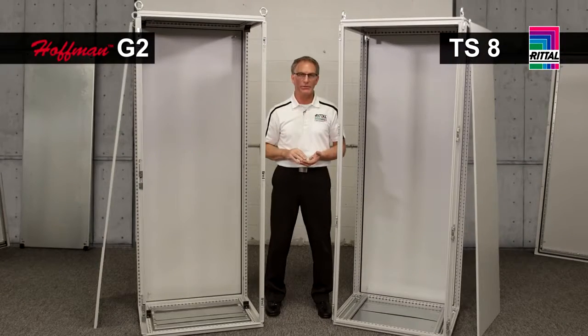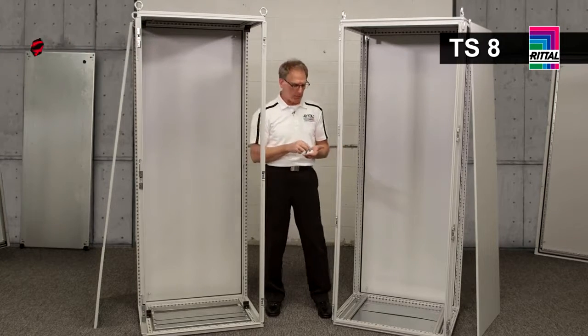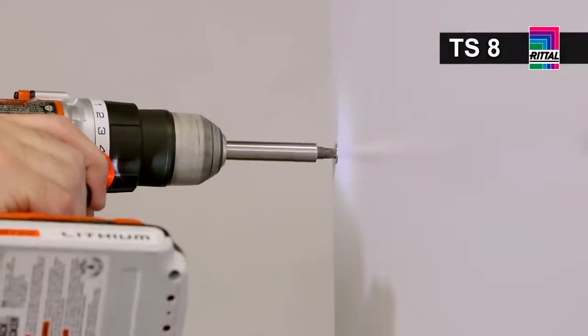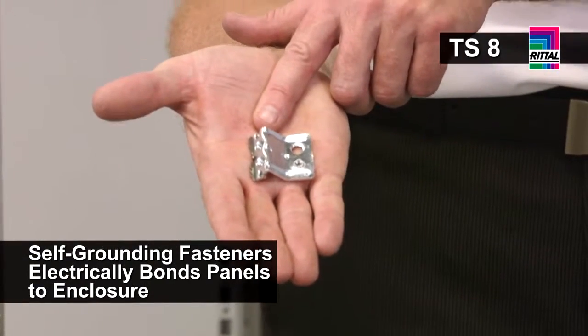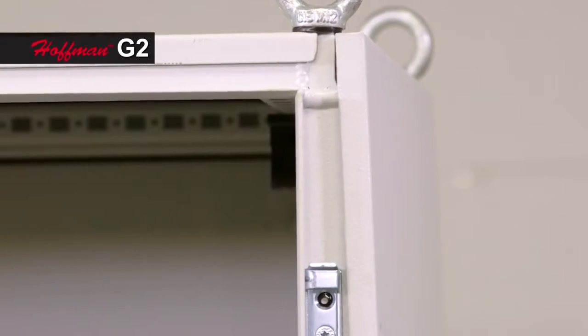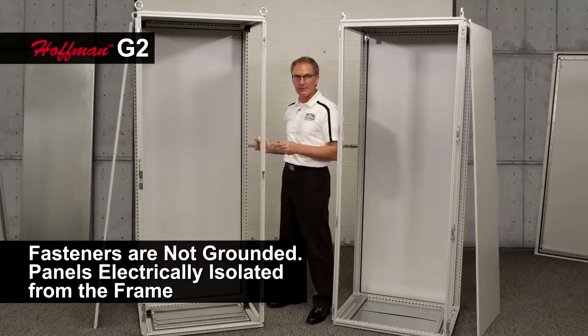One of the biggest design benefits of a modular enclosure system is the ability to create large bays of enclosures by interconnecting enclosures together. To maintain the NEMA rating and complete the construction, you'll need sidewalls, whether it's a standalone cabinet or a cabinet at the end of a row. Rittal handles this with metal clips that attach to the enclosure frame — we hang the panel, six screws are put into place, and Rittal uses a unique fastener with grounding teeth that provides electrical bonding of the panel back to the enclosure frame. In the G2 ProLine, a plastic clip is attached to the sidewall, the panel balances on the enclosure frame, and after inserting six fasteners, the panel is electrically isolated from the enclosure frame.